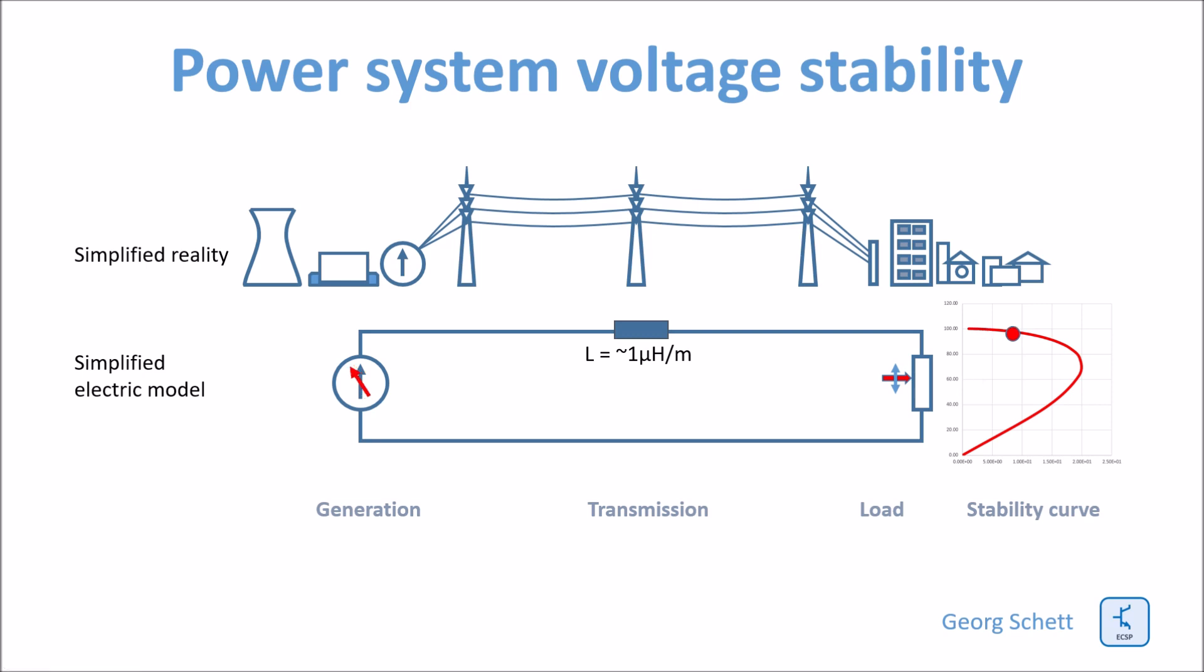So when I increase the load, I reduce the voltage. You see that there will be more and more voltage drop across the line. Therefore, the curve will approach a tipping point, and above the tipping point, the voltage will collapse.